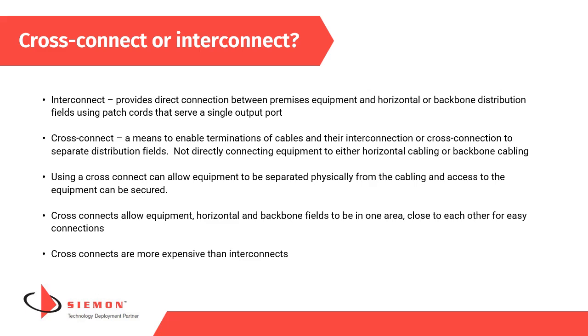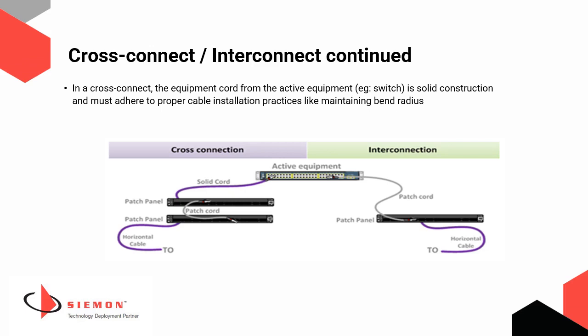That's enough time, so we will move on to the next slide and differentiate. Looking at this visual, we have network equipment for both options. In a cross-connect design, the switch ports are replicated onto an equipment patch panel and patching is carried out between the equipment patch panel and the distribution patch panel. We recommend that the switch links between the active equipment and the active patch panel be solid core cable, as stranded cable can have length limitations or the equipment patch panel terminations may not accept stranded conductors.